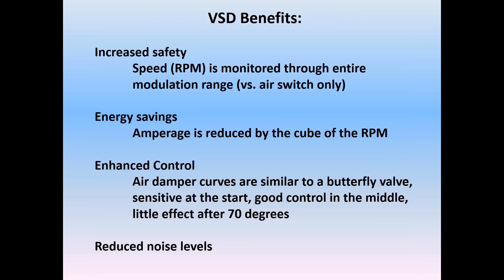It's a good time to list the four benefits of a burner that is equipped with a variable frequency drive. Number one reason, again, is safety. No price can be placed on that. While the air pressure switch is important and a long-standing safety device, it really only protects you at low fire, where a drop is detected. The speed sensor provides safety at all firing rate ranges.